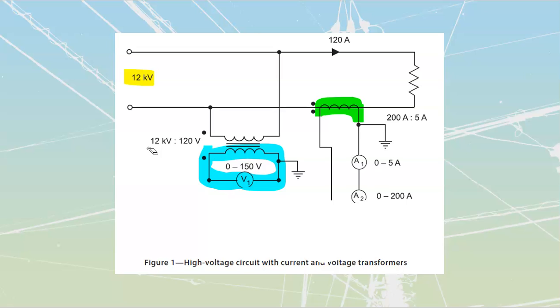We'll cover all of that in grounding and bonding, but we are grounding down for safety on that other side, so we don't have a floating value of voltage, and this just helps any overcurrent protection operate if we would have it inside of that circuit. We don't here, so we're not going to try and explain that, but it's just a good practice that if I've got low voltage transformers, I'm going to ground down one side.